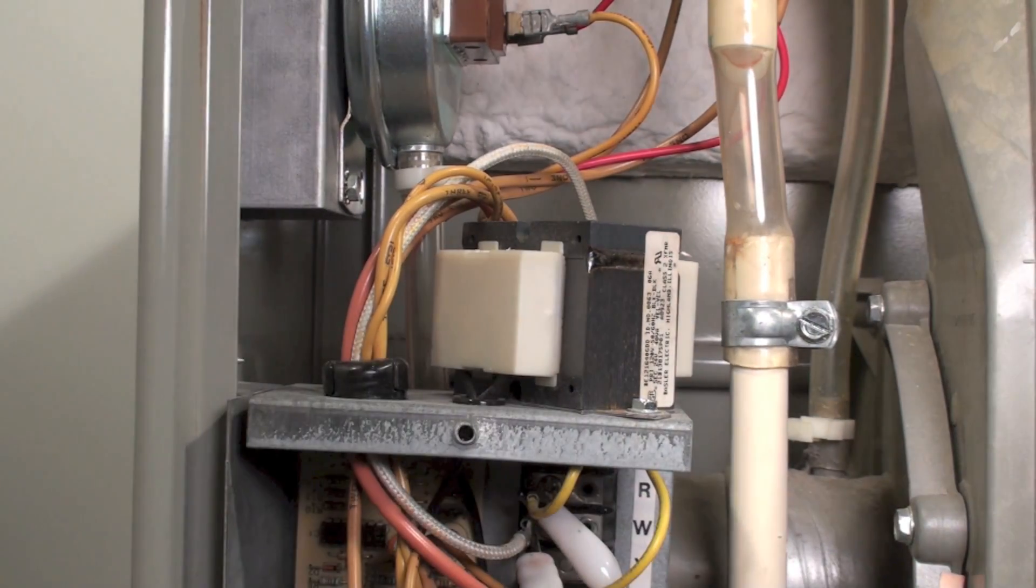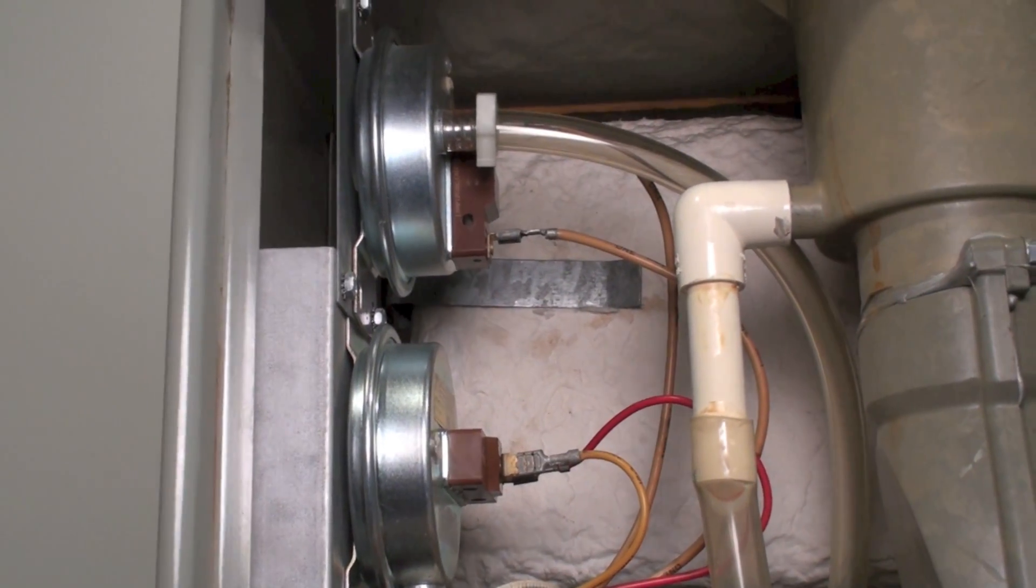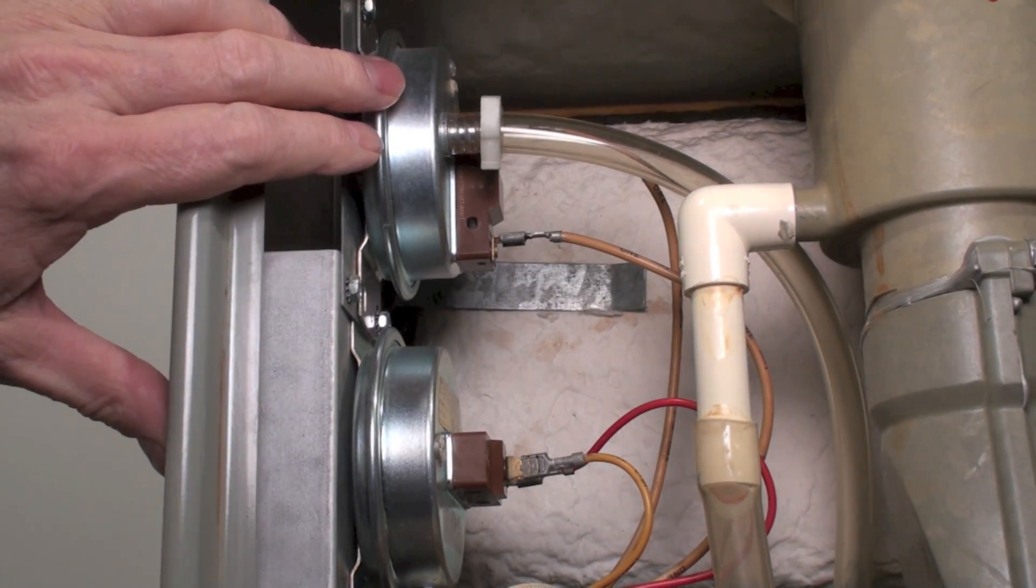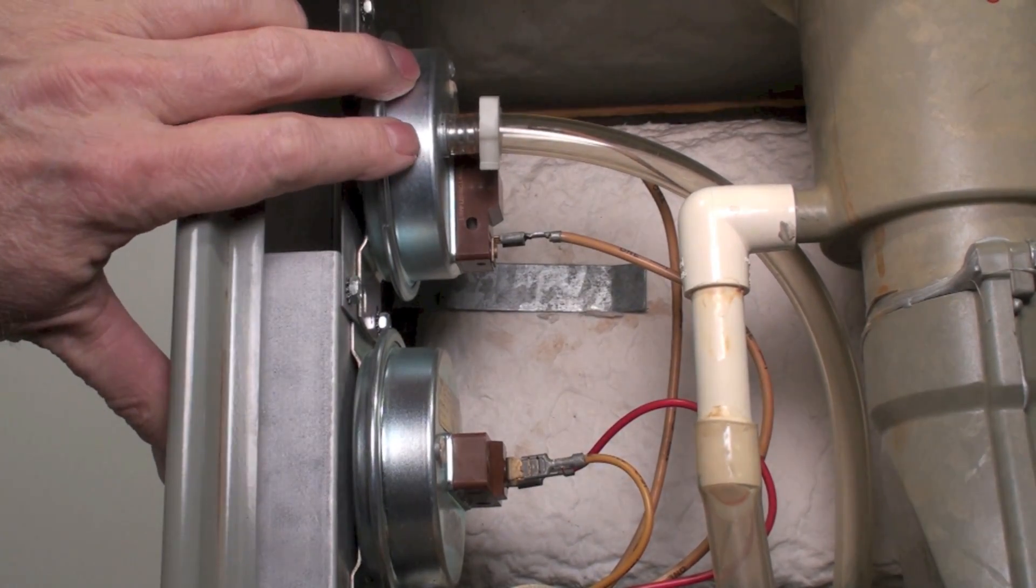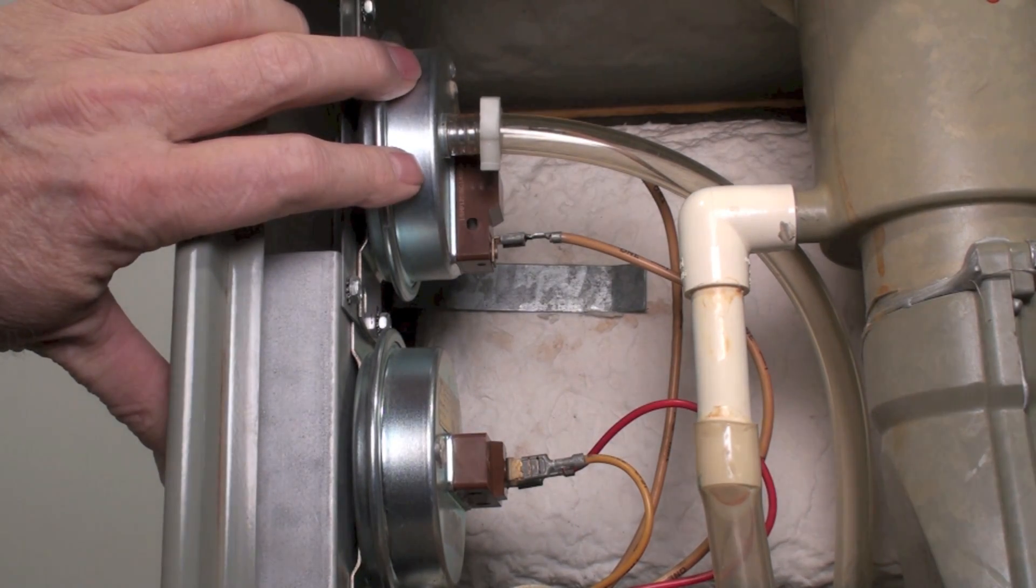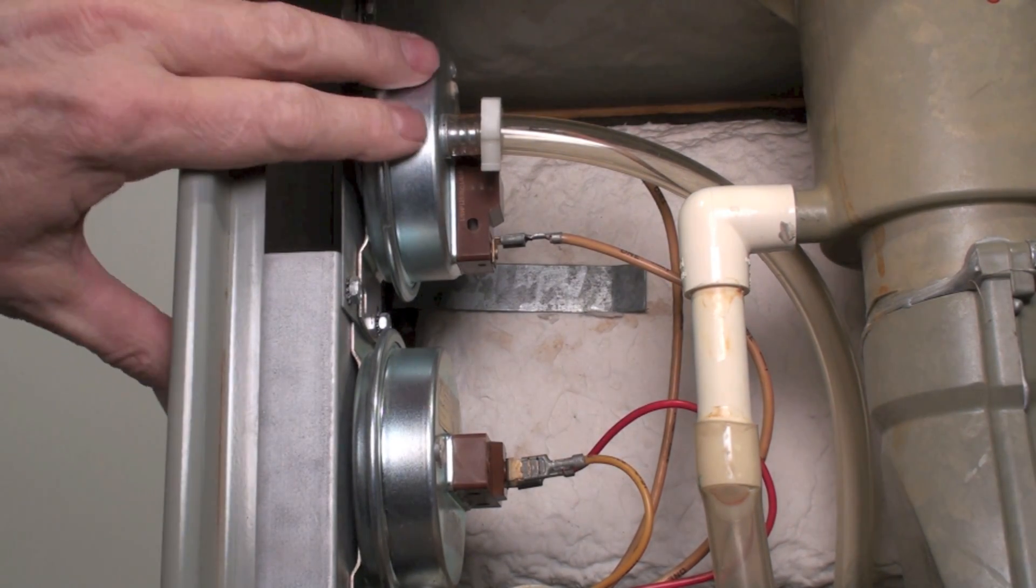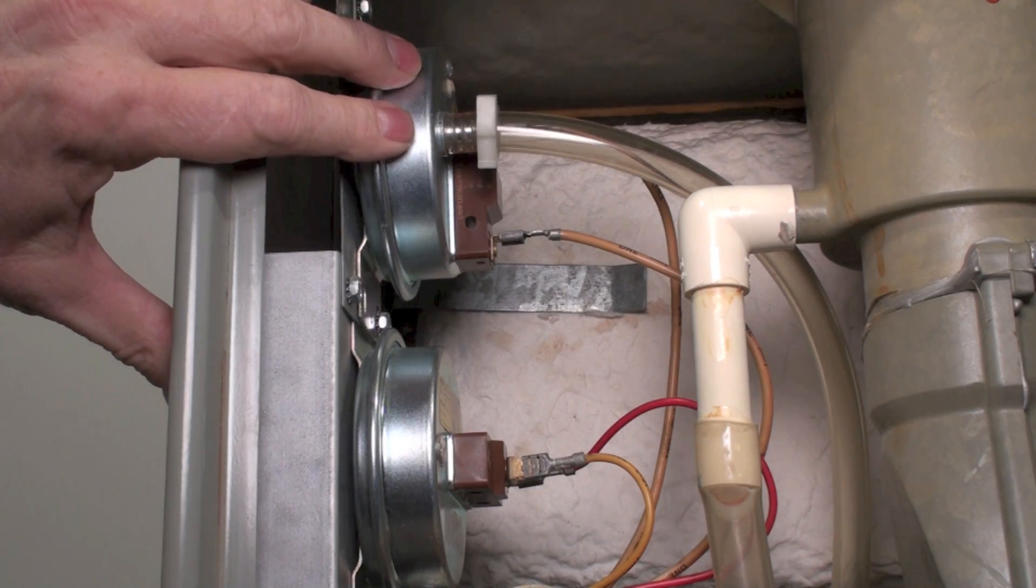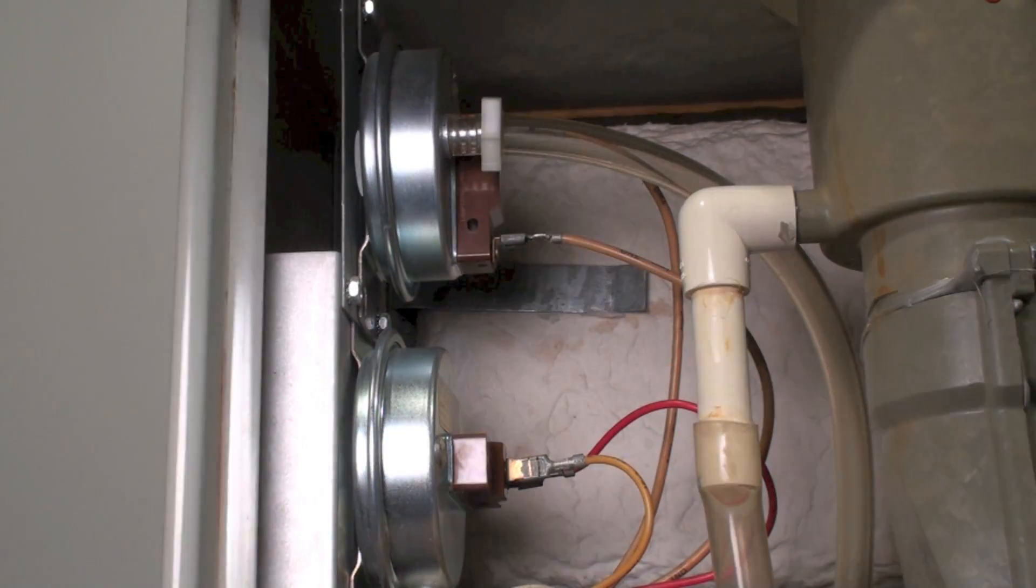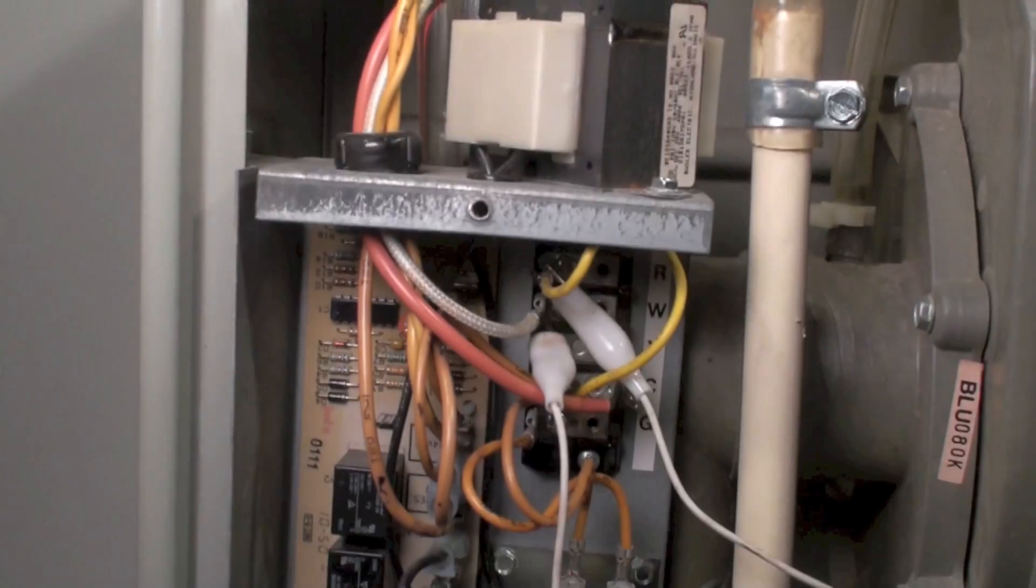What it does is when the pressure drops—this is negative pressure—when the pressure drops to a certain vacuum, then this closes. When it closes, that little circuit board down below that we were looking at a minute ago sees that the pressure switch has closed and it starts a short timer.